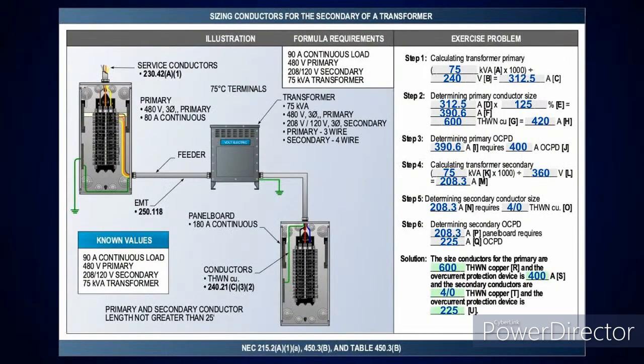Now, here's the 3-wire. Now, when you look at this and you start sizing the transformer going over there, let's look at what we've got. We have a 480 volt 3-phase. We've got 80 amps of continuous load. I'm sorry, 90 amps of continuous load. And you come in and you start looking at everything that's here. They're also going to tell you we've got 208 volt, 120 volt secondary and a 75 kVA transformer.